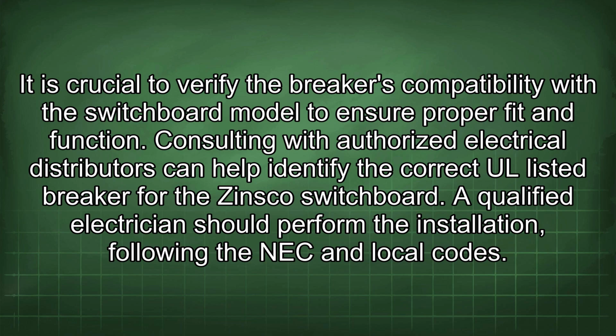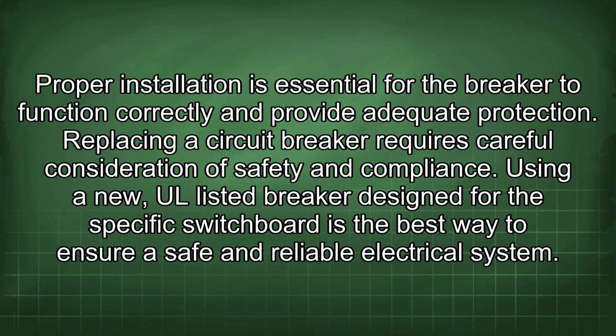Consulting with authorized electrical distributors can help identify the correct UL-listed breaker for the Zinsco switchboard. A qualified electrician should perform the installation following the NEC and local codes. Proper installation is essential for the breaker to function correctly and provide adequate protection. Replacing a circuit breaker requires careful consideration of safety and compliance.